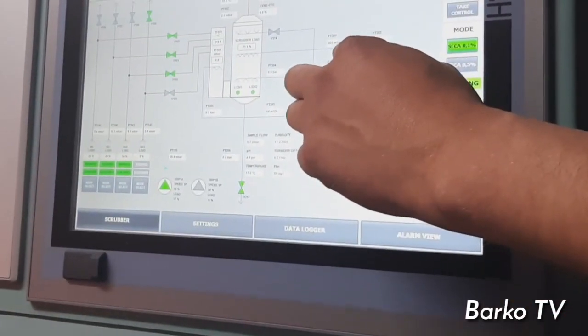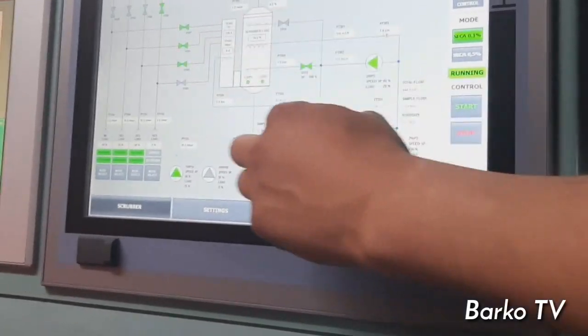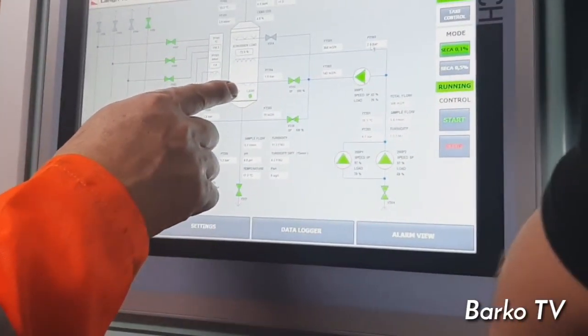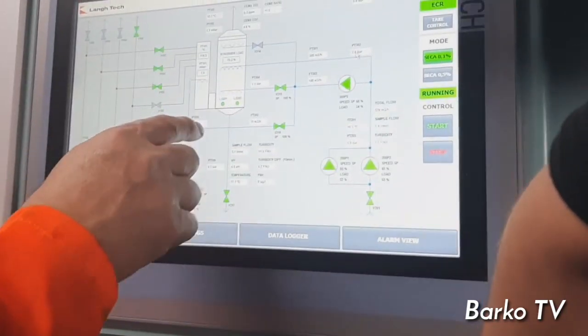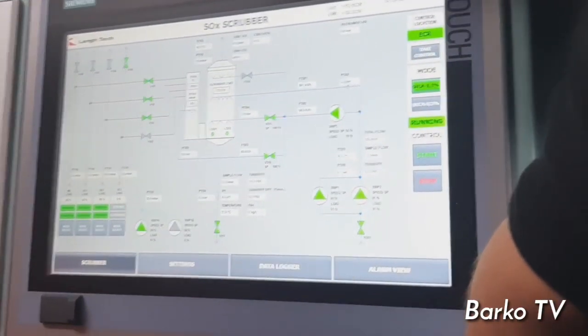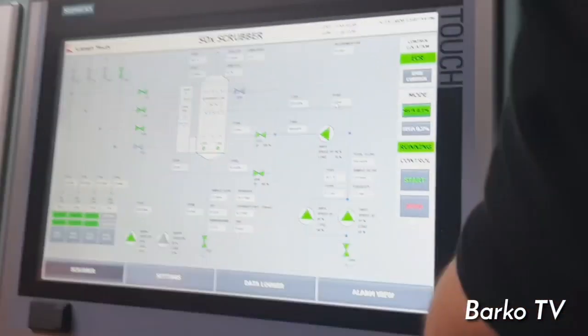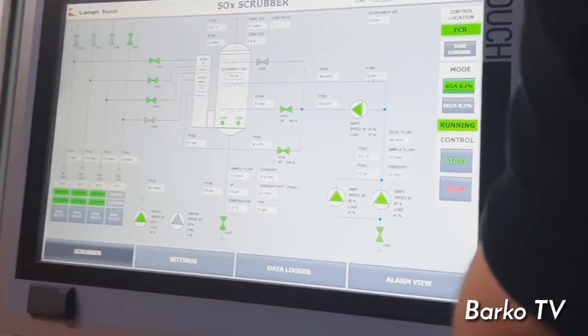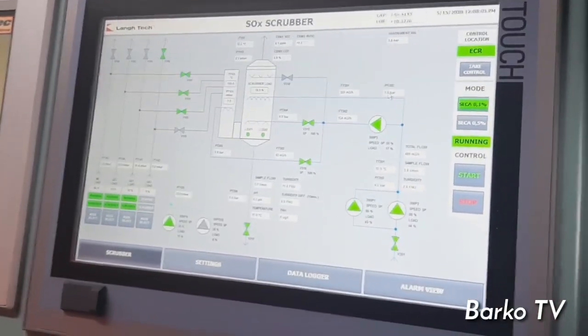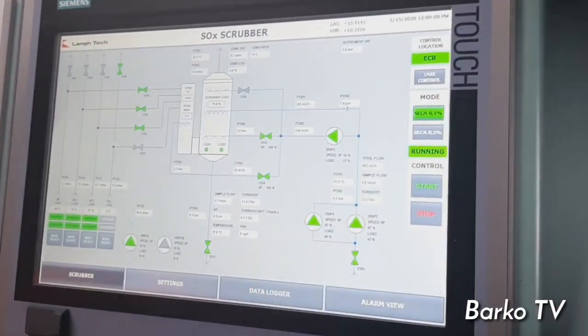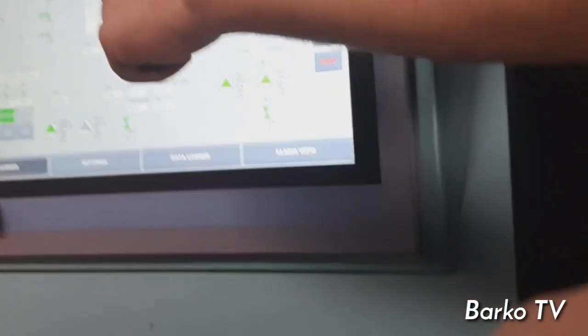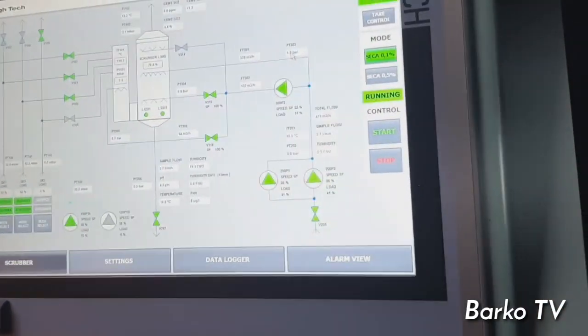Some of the water is pulled by the booster pump going to the booster line and also the pre-cooling line. The spray at the bottom also cools — we call it the booster line but it functions like a cooling or quenching line. It is important to cool down the gas because otherwise the water will evaporate and there will be no reaction between the sulfur and water. That is why we have to cool down the gas first. Then the gas rises to the part where the packing bed is.